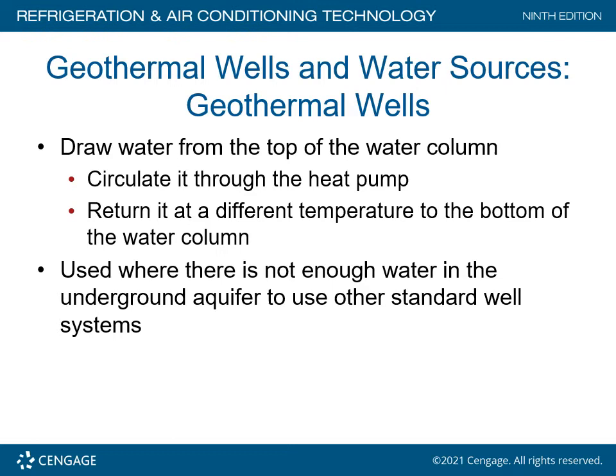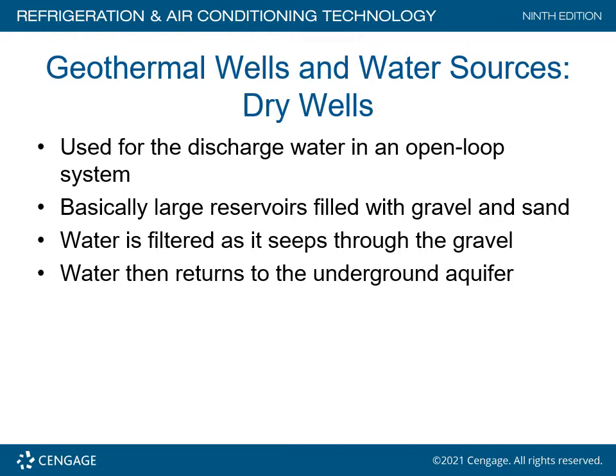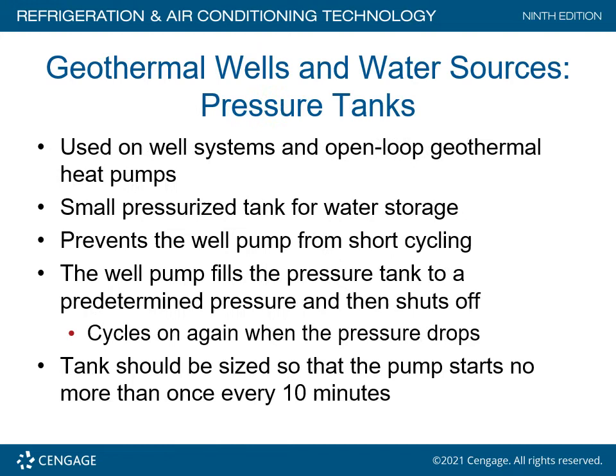Geothermal wells draw water from the top of the water column, circulate it through the heat pump, and return it at a different temperature to the bottom of the column. This is used where there is not enough water in the underground aquifer for standard well systems. A dry well is used for discharge of water in an open loop system — it is a large reservoir filled with gravel and sand, where water is filtered as it seeps through and is returned to the underground aquifer.